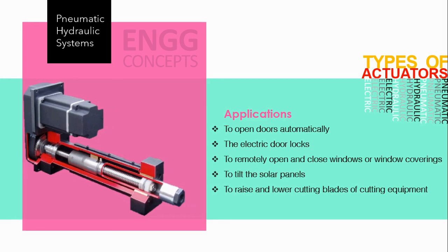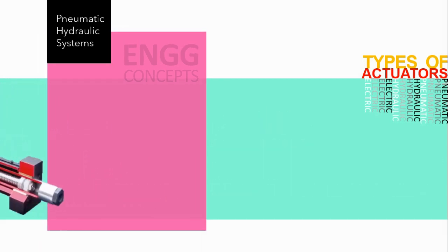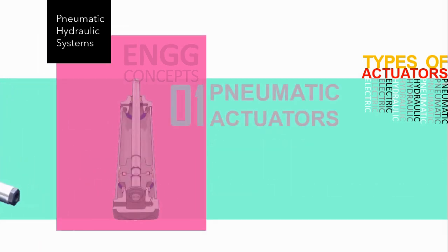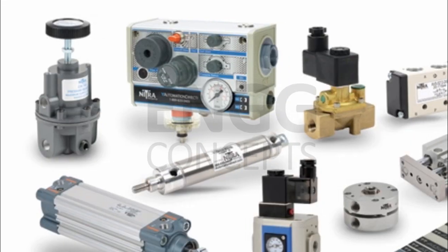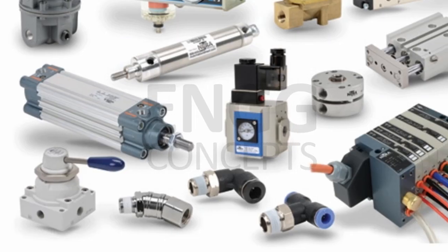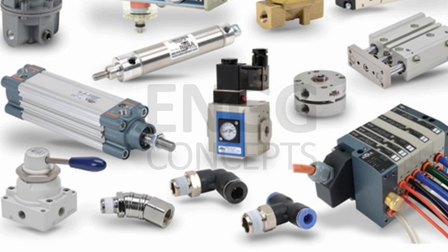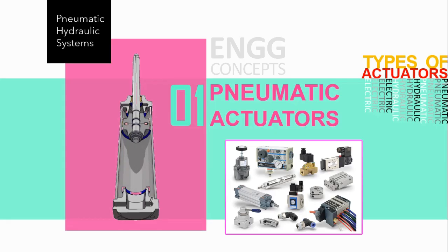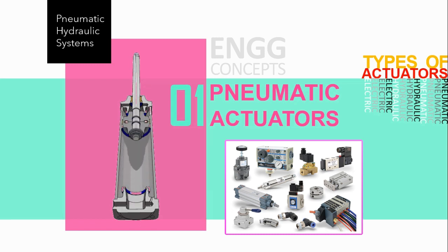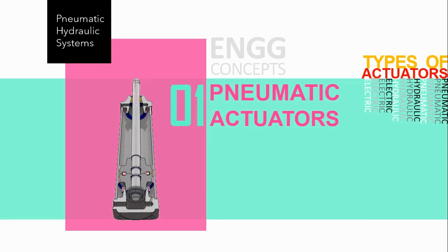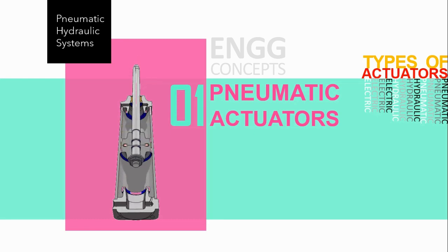Actuators are all around us — in manufacturing plants we can use actuators to operate valves, fluid couplings, and dampers, to name a few. Pneumatic actuators can utilize a cylinder, diaphragm, or a rotary vane design. Compressed air acts upon a piston to move it in one direction; a counter force consisting of a spring or a second volume of compressed air is applied to the opposite side of the piston to reverse or maintain a position.